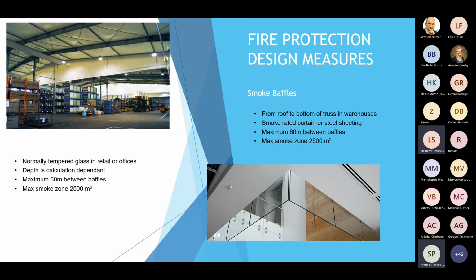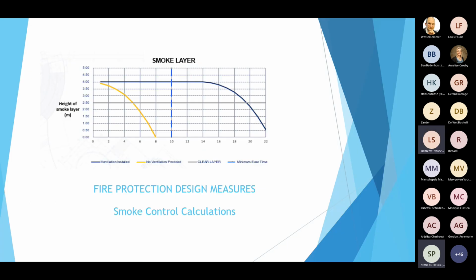Again, it's to compartmentalize your smoke movement, and based on that compartmentalized area, you'll have either your vents or your smoke zones and your smoke fans in order to ventilate and to keep the area clear for what is noted in the code. And obviously a smoke design is not just a smoke design. It refers to smoke calculations, which is an Excel spreadsheet that we've created. And the long and the short in the image that you see there is basically you need to adhere to a 2.5 meter smoke layer.